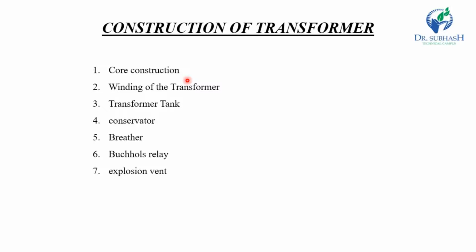Magnetic circuit. The magnetic circuit of a transformer consists of core and yoke, and it provides the path for the flow of magnetic flux. The transformer consists of a laminated steel core and two coils. The two coils are insulated from each other and also from the core. The core is constructed from laminations of steel sheet or silicon steel, assembled to provide a continuous magnetic path. At usual flux density, the silicon material has low hysteresis losses. The vertical portion on which the coil is wound is called a limb, while the horizontal portion is called a yoke.